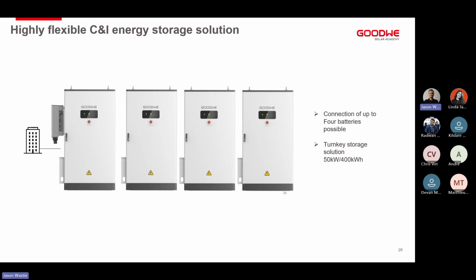These batteries, we can connect up to 4 of them per inverter, meaning we can go with a 50 kilowatt inverter and 400 kilowatt hours of battery, and up to a maximum of 500 kilowatts and 4 megawatt hours of battery connected onto one system or plant.